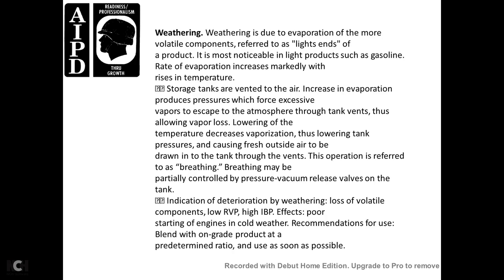Storage tanks vented to the air allow excessive vapors to escape to the atmosphere through tank vents, causing vapor loss. Lowering the temperature causes vaporization pressure to lower, drawing fresh outside air into the tank through the vents — this operation is referred to as breathing. Breathing may be controlled by pressure-vacuum relief valves on the tank. Indications of weathering deterioration include low Reid vapor pressure or high initial boiling point. Effects include poor starting of engines in cold weather. Recommendation: blend the product on-grade at a predetermined ratio as soon as possible.